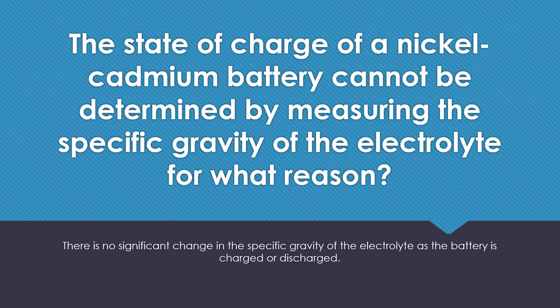The state of charge of a nickel-cadmium battery cannot be determined by measuring the specific gravity of the electrolyte — for what reason? There is no significant change in the specific gravity of the electrolyte as the battery is charged or discharged.